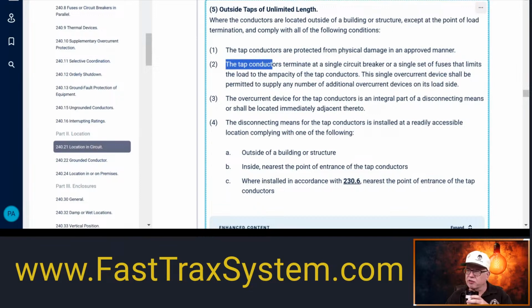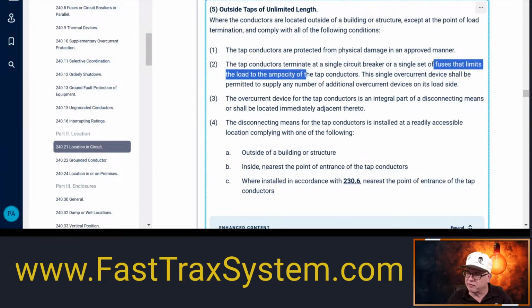Next, the tap conductors terminate in a single circuit breaker or single set of fuses. Again, we see the same language that limits the load to the ampacity of those tap conductors. Whatever the load is in the calculation and whatever the size of those conductors are, the overcurrent protection has got to limit it so that those conductors won't see more current than the overcurrent device allows at the point of termination. So you have to correspond. If it's a 200 amp overcurrent device, then those conductors would have to have an ampacity that is protected by the overcurrent protective device, right?